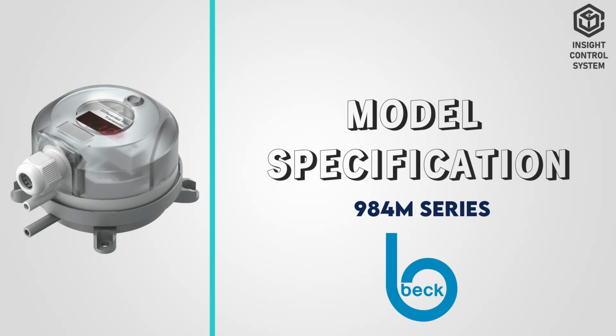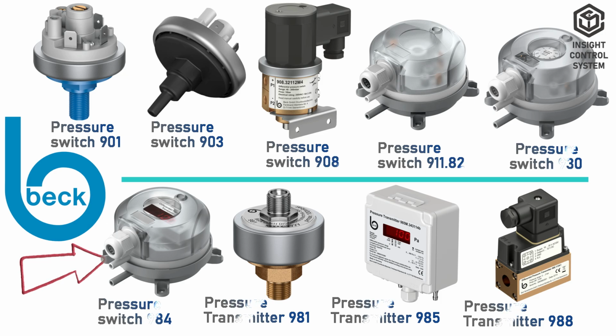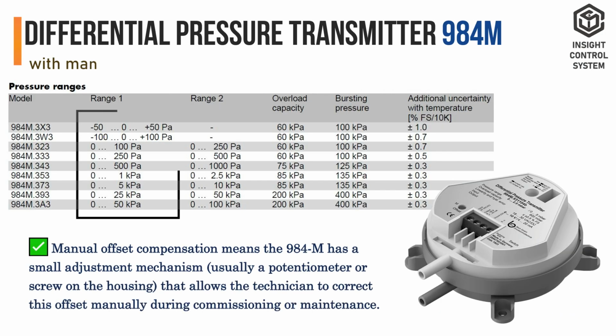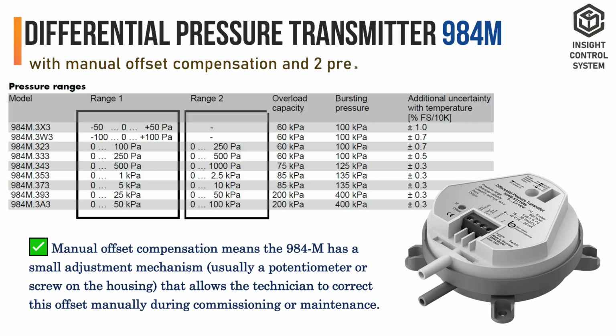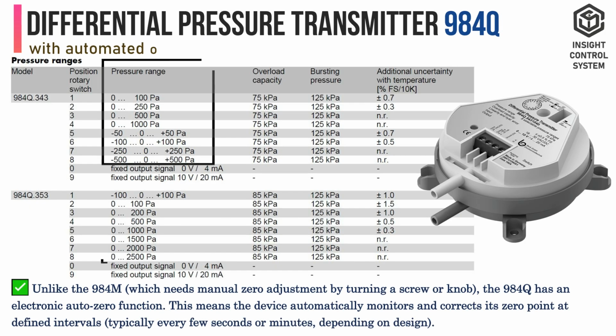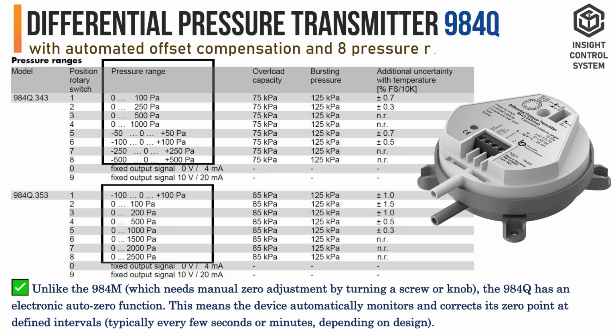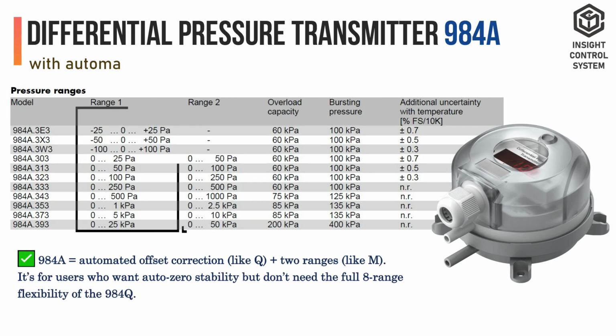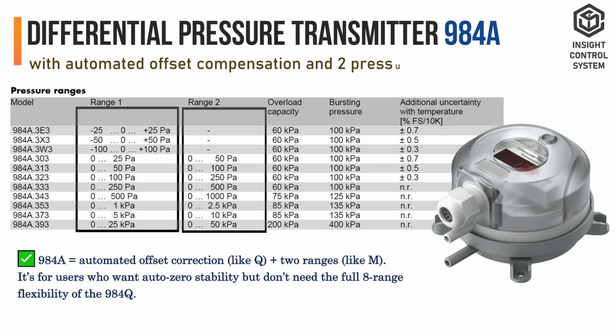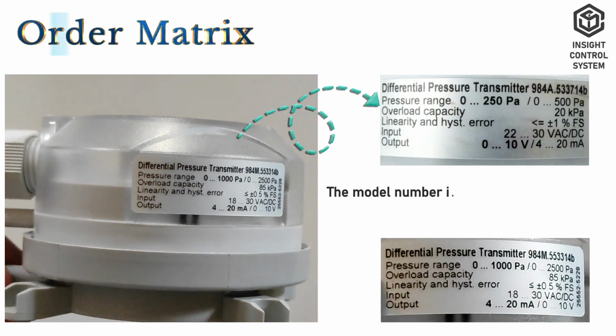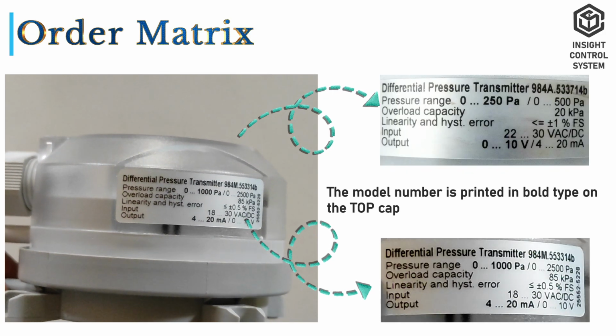Model specification: 984 is represented as the series of a Beck product family. The 984M series has manual offset compensation and 2 pressure ranges. The 984Q series has automated offset compensation and 8 pressure ranges. The 984A series has automated offset compensation and 2 pressure ranges. The model number is printed in bold type on the top cap.